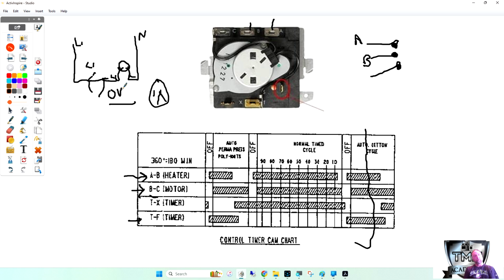So whenever you do voltage, I want you guys to use the actual load, the light bulb, the motor, whatever. And if you don't have voltage there, only move 1 meter lead back to find where the voltage is. How far did it go? But going back to what I was saying, I want to check this switch for ohms or continuity. Unplug the machine, disconnect at least one wire, and test it.